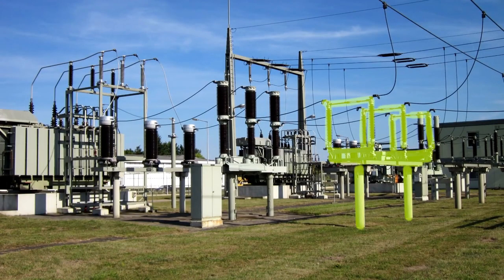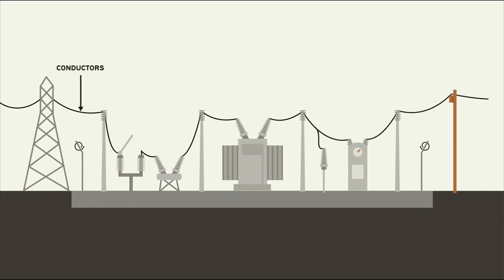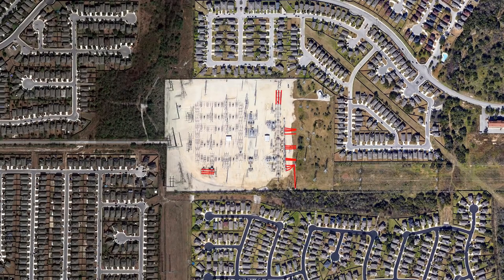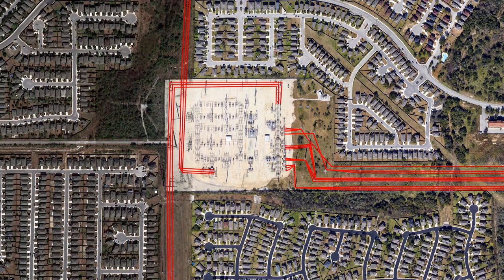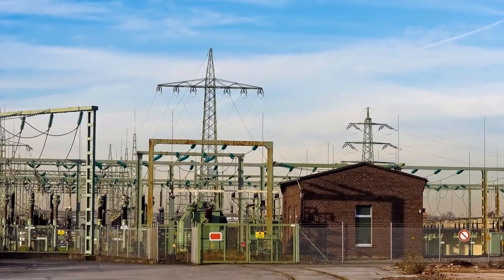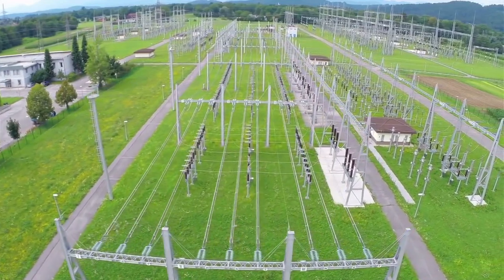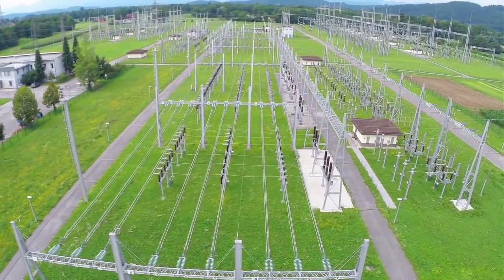The first and often simplest of these roles is switching. The general layout of a substation consists of some number of electric lines — called conductors if you want to fit in with the electrical engineers — coming into the facility. These high voltage conductors connect to a series of equipment before heading out to their next step in the power grid. As a junction point in the grid, a substation often serves as the termination of many individual power lines, creating redundancy and making sure the substation stays energized even if one transmission line goes down. The connections to these various devices are called buses, often rigid overhead conductors that run along the entire substation.